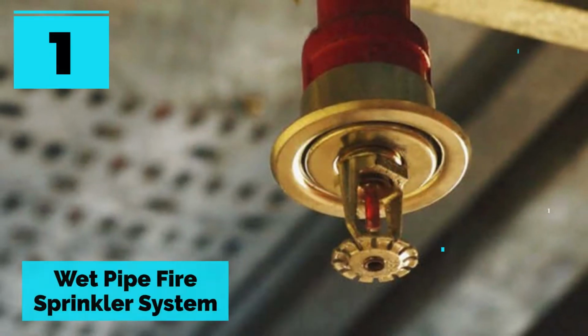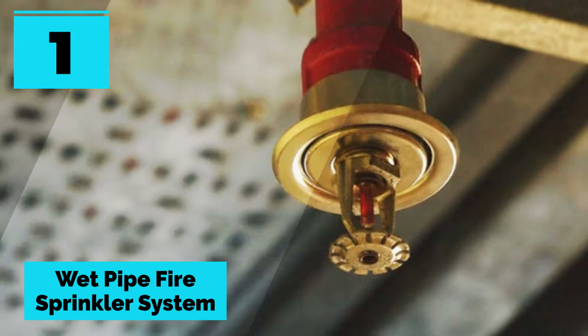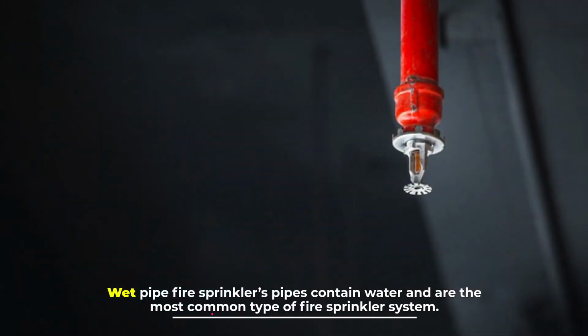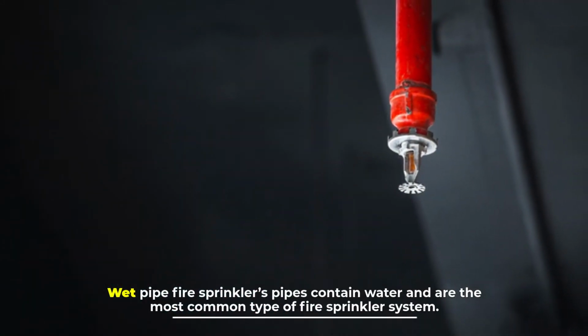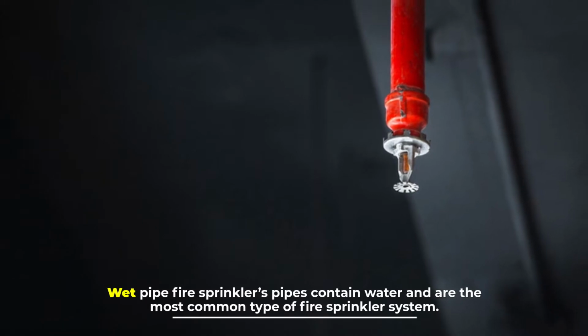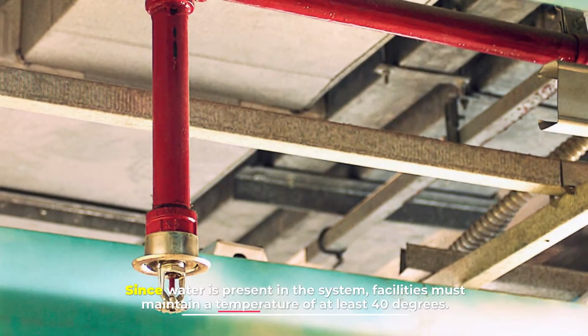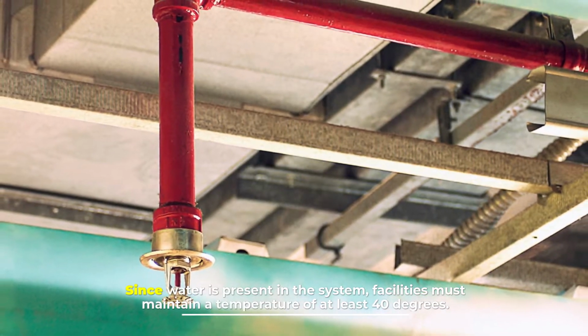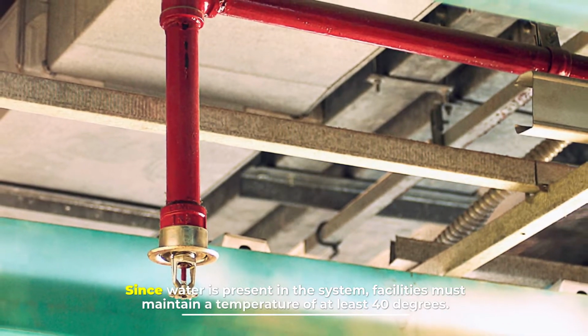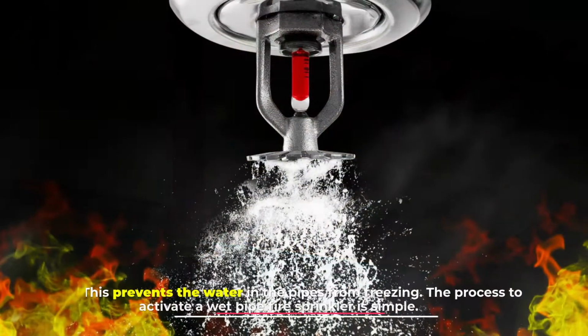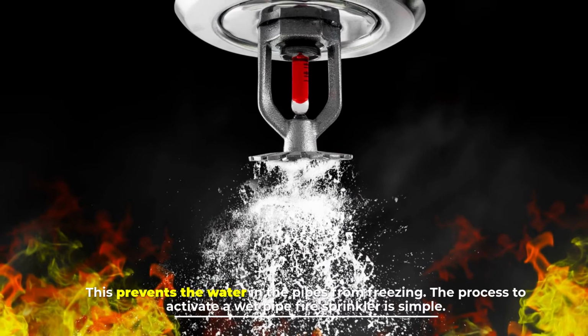Number 1. Wet pipe fire sprinkler system. Wet pipe fire sprinkler pipes contain water and are the most common type of fire sprinkler system. Since water is present in the system, facilities must maintain a temperature of at least 40 degrees. This prevents the water in the pipes from freezing.